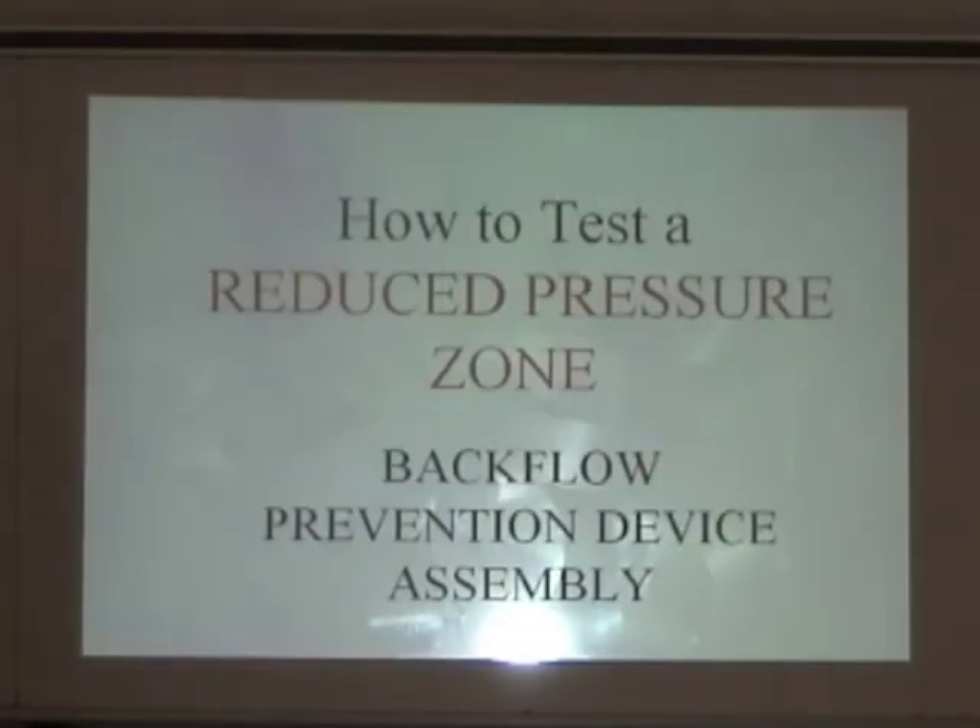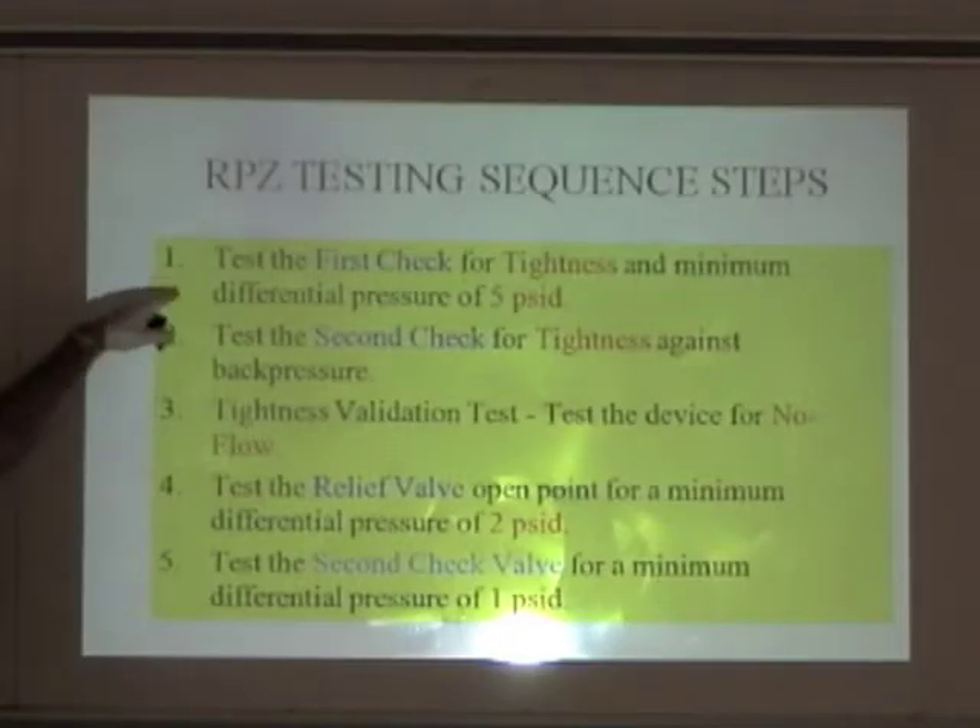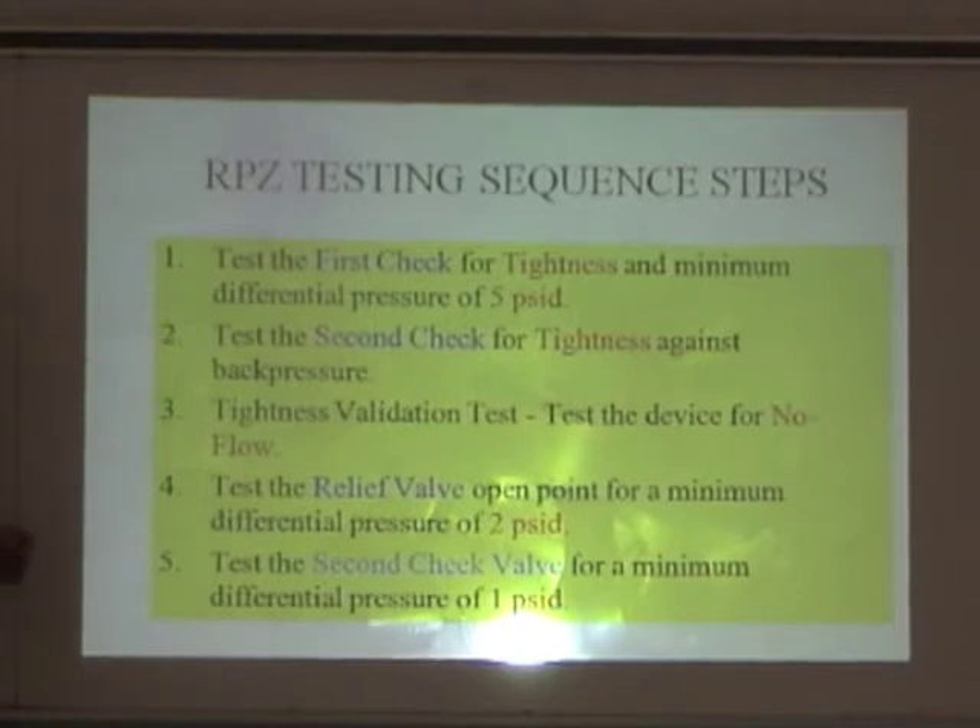We're testing a reduced pressure zone backflow prevention device. The first thing we're going to do is test the first check valve for tightness and measure the pressure differential. Then we're going to test the tightness of the second check valve under back pressure. We're going to test for no flow — the test is exactly the same as our double check valve. We're going to test the relief valve to see when it opens, and we're going to test the pressure of that second check valve as well.